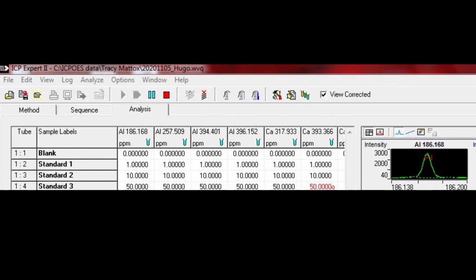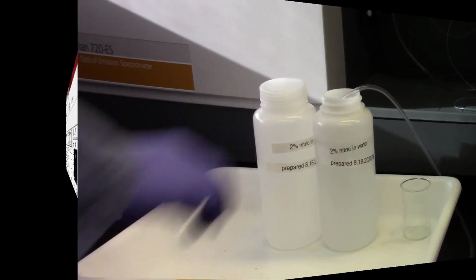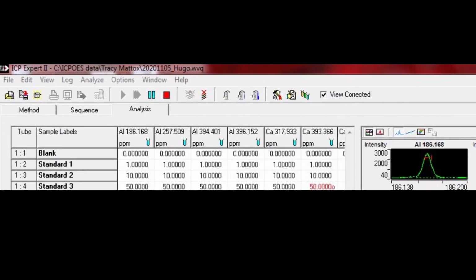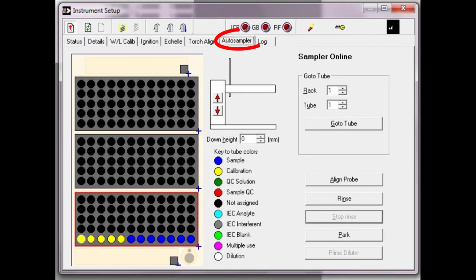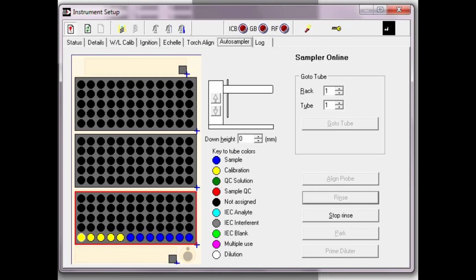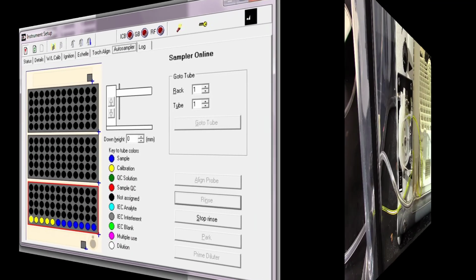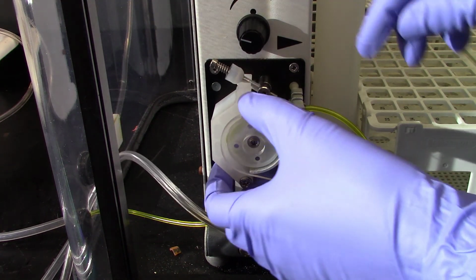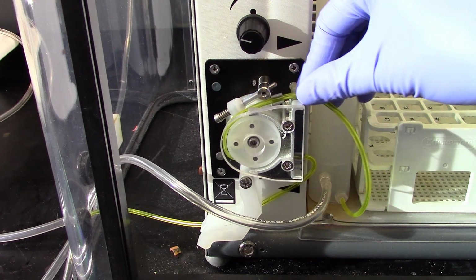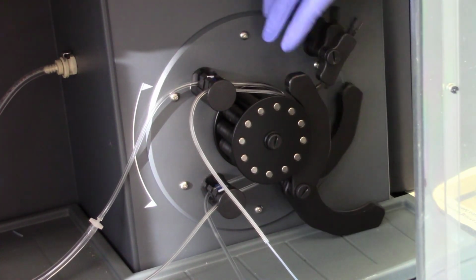If you have not done so already, turn off your torch by pressing the icon with 3 lines under a red X. This can be done as soon as the analysis has been completed. Before disconnecting the tubing, it's important to flush out all of the solvent. Remove the tube from the wash solution. Then press the hammer icon and select the Auto Sampler tab. Turn on Pump Fast and rinse. After about 5 minutes, the tubing will be dry. Stop the pump and the rinse. Then release the tubing from the auto sampler, and release both sets of tubes on the ICP itself.